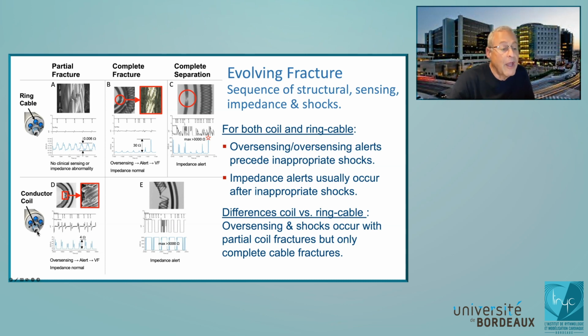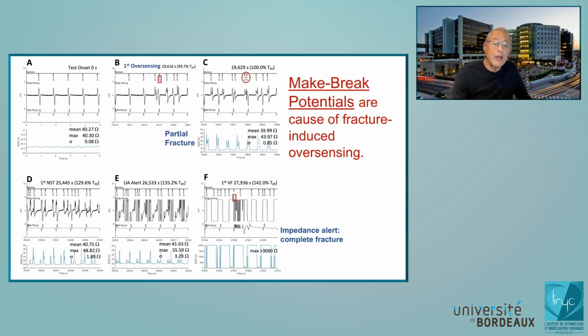Similarly, differently for a coil, when you have a partial fracture, you do get oversensing because there are only four filars or three filars, depending on the coil we're dealing with. And there's no constraining inner insulation to hold it in place, so they can flex more. And we also only get impedance alerts when we have a complete separation. So now we know what it takes to come up with our diagnostics.